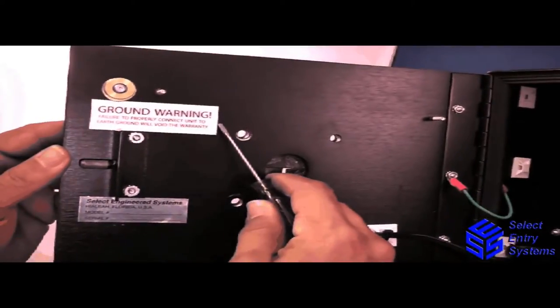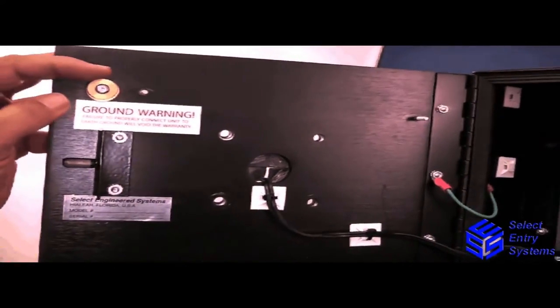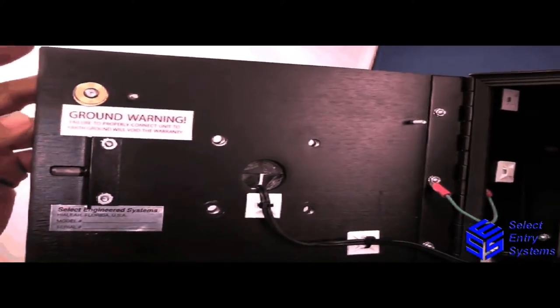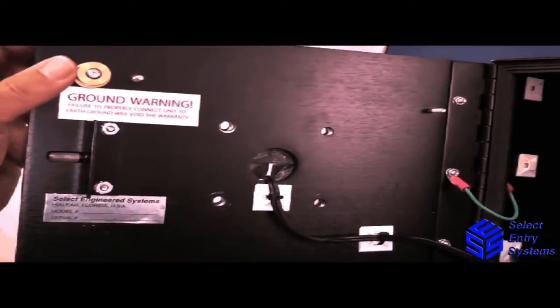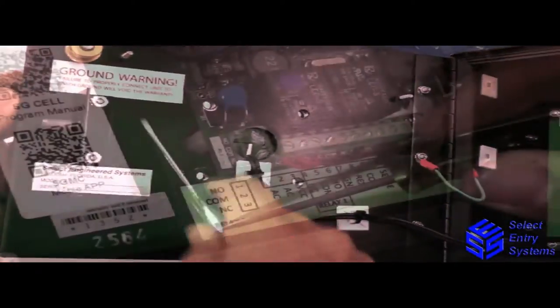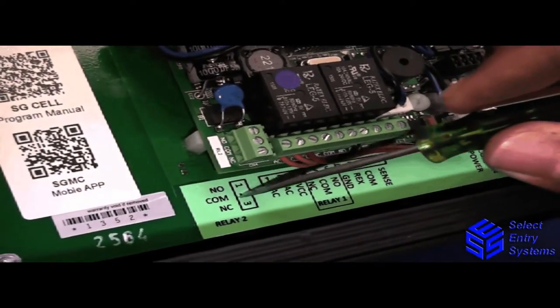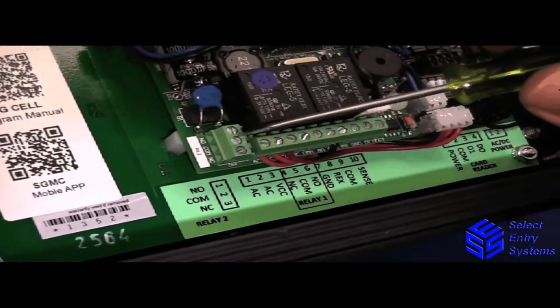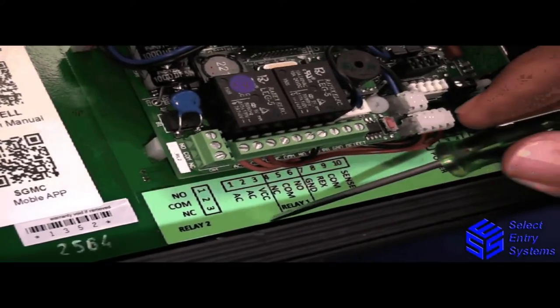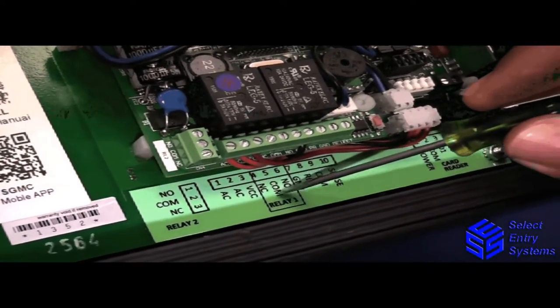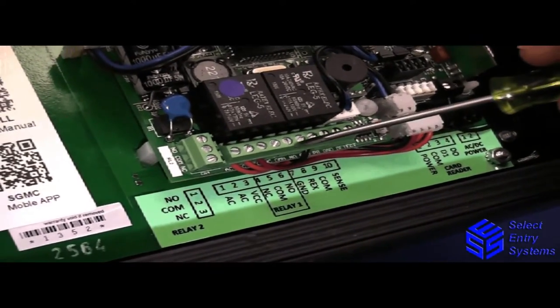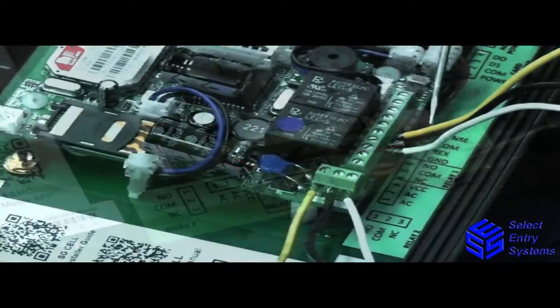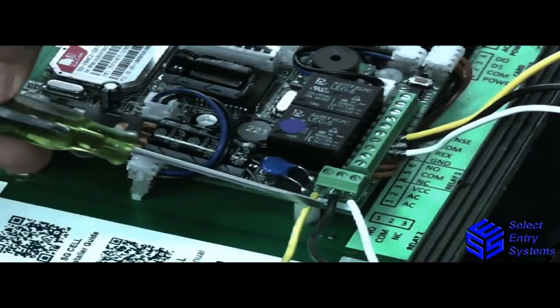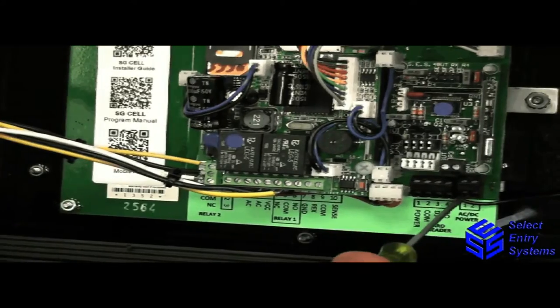The CSG must be grounded to a good earth ground. Use at least a 16-gauge wire not more than 25 feet from the CSG to the earth ground rod. Here, we will see your relay locations and connections, followed by the power connections.